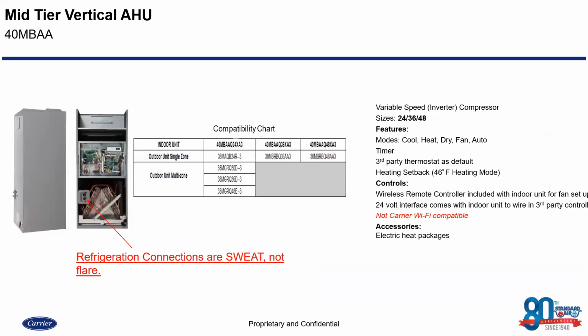One important thing to note with this 40 MBAA, unlike other ductless units which have flare connections, the refrigeration connections on this vertical air handler are sweat, not flare, which means we're going to have to do some brazing on this system. Now, this does not mean that we can put a filter dryer on this system. That principle and rule still remains the same.